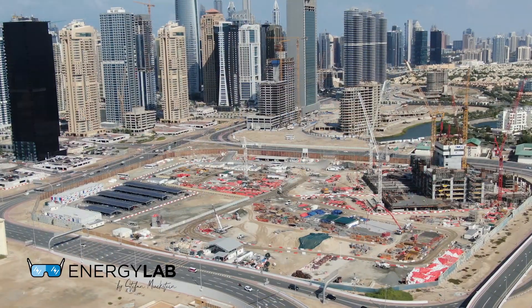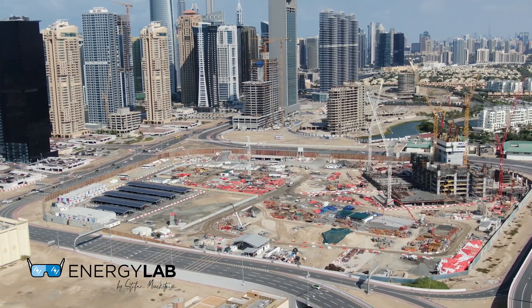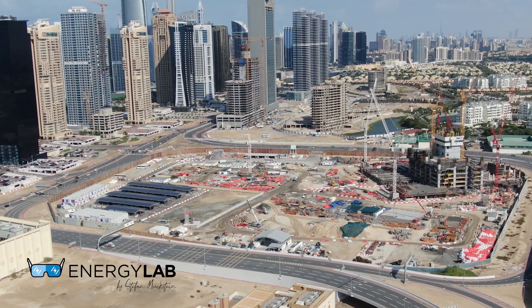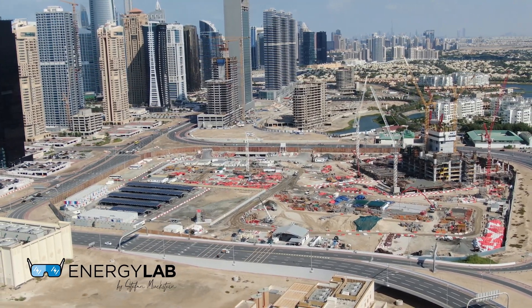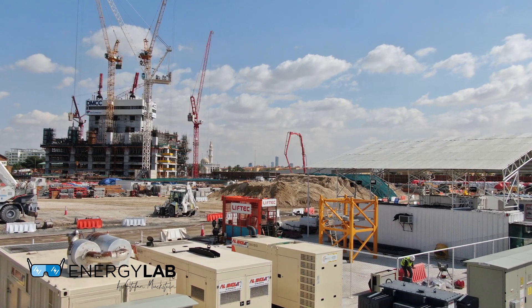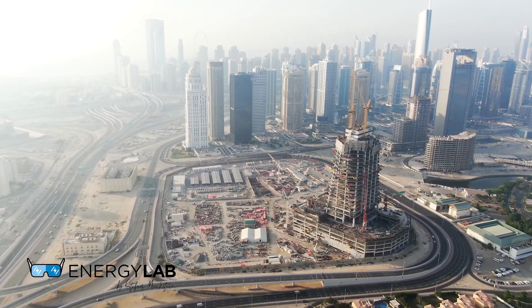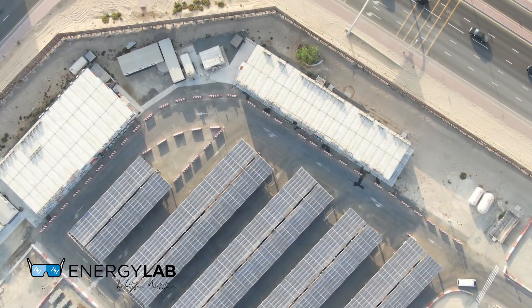Before the site tour, I'd like to explain what we're doing with the project. Typically on construction sites, multiple power requirements are distributed across the site and construction companies place a diesel generator relatively close to where energy is required. What we've done differently is centralize power generation in one location and distribute loads locally, while using a medium voltage network to transmit power to remote areas. We've effectively powered all site offices, labor rest facilities, and tower cranes on a single network using solar.